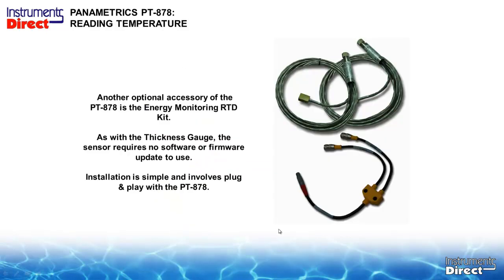Now, the newer kits are much more convenient. With the older kits, you had a terminal block and all kinds of wires coming out of it. Now, you have some precision strap-on RTDs that go on the outside of the pipe, and we give you some thermal coupling compound. It looks like zinc oxide, real thick, gooey stuff. Those get plugged into this Y connection, which basically takes the 4-20 milliamp signal out of these temperature sensors and runs it right into your I/O port.